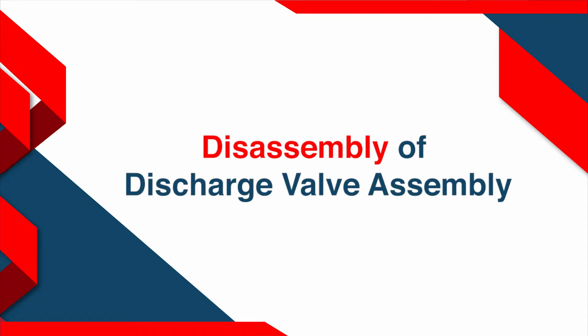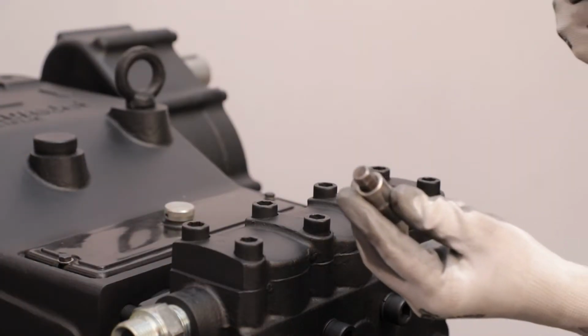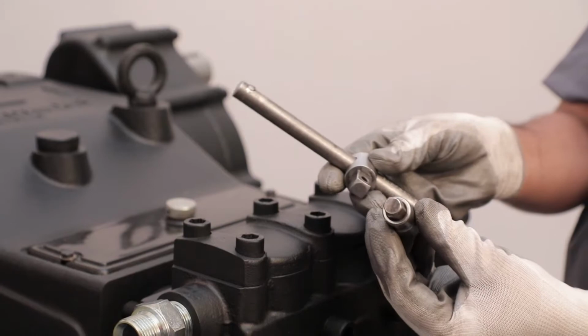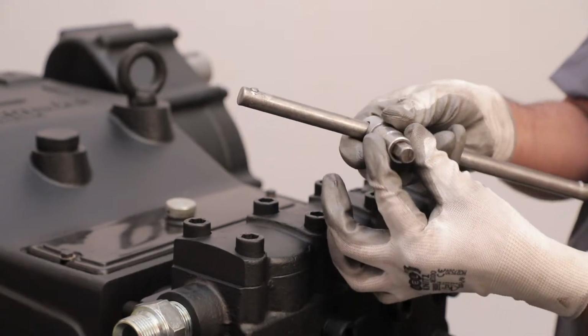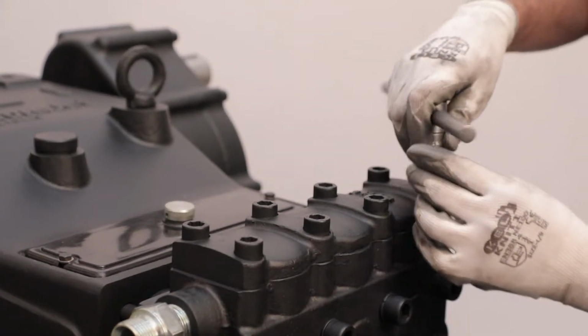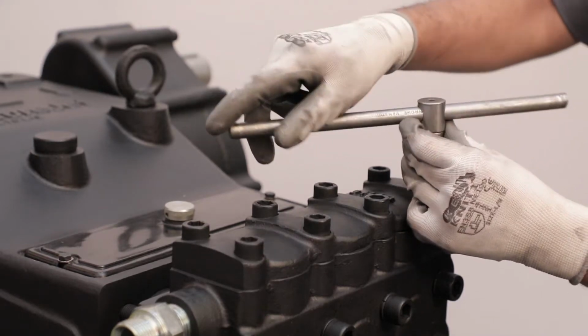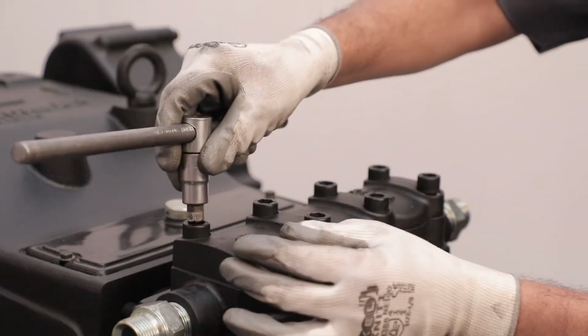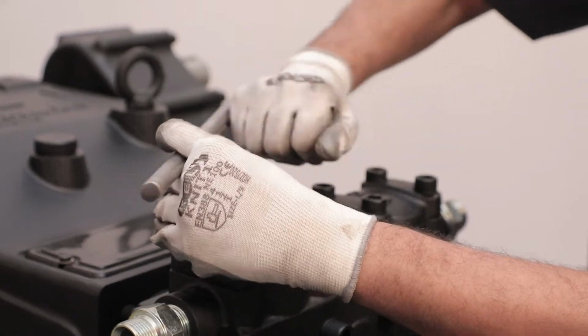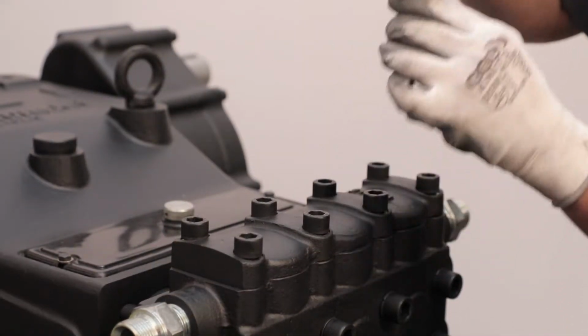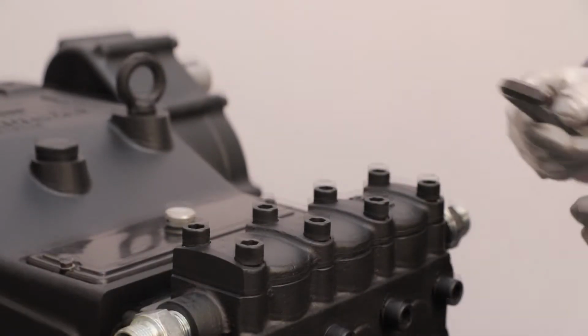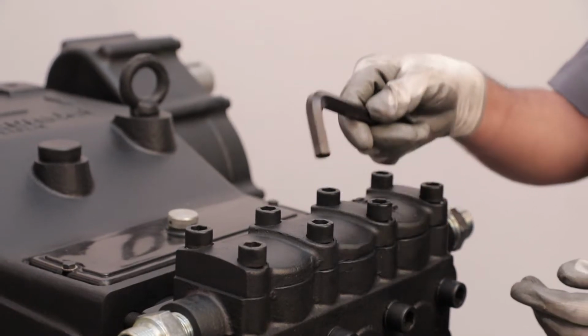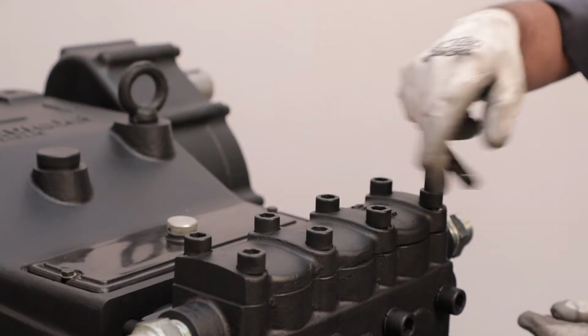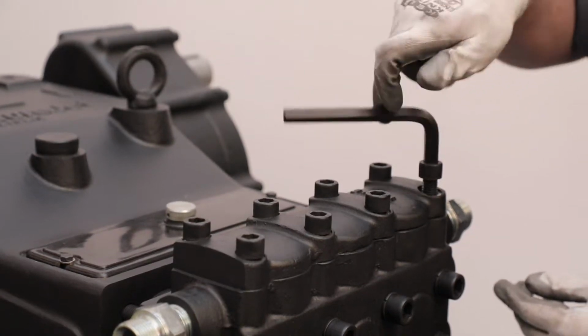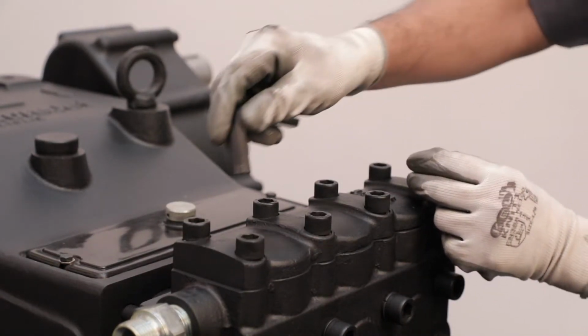Disassembly of discharge valve assembly. First of all, take Allen key socket and wrench and loosen all 8 M16 by 180 cap screws to dismantle suction and discharge valve holder cover. Then, with the Allen key, unscrew all cap screws and separate suction and discharge valve holder cover from the pump head.